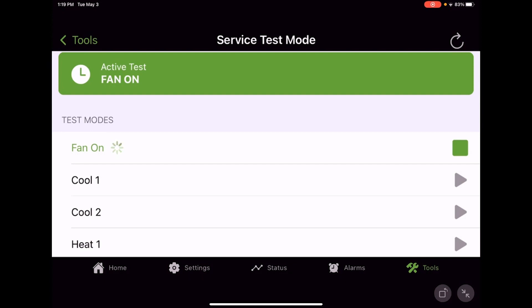There is a service test timer that you can adjust up to 120 minutes or two hours. So it is adjustable. It's advisable to go check that just so you know where it's at in case anybody has changed it, but it is adjustable, and again by default it is one hour.